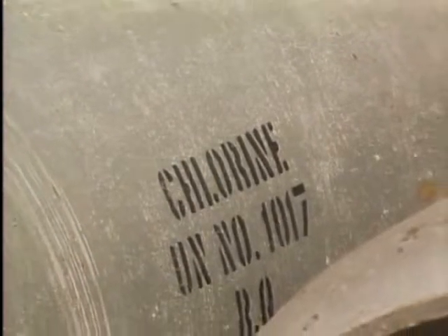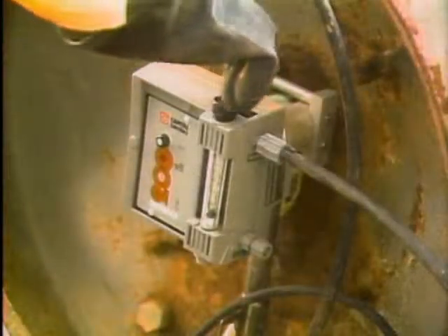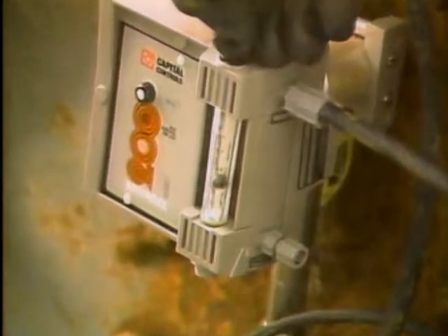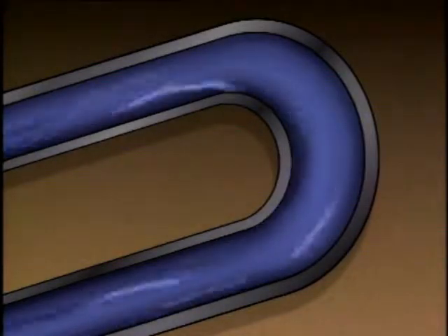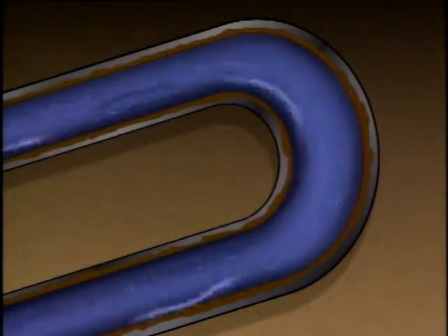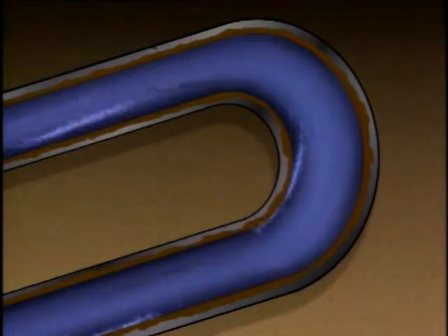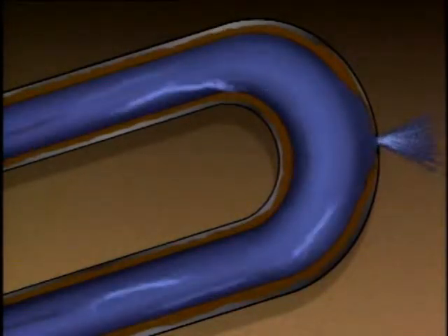Fouling can sometimes be minimized by adding chemicals to the fluids passing through a heat exchanger. For example, chemicals such as chlorine are often added to cooling water to reduce the amount of algae or other organisms inside a unit. Corrosion chemically deteriorates tube metal to create a leak. Corrosion is caused by a chemical reaction between the metal in the heat exchanger and either the fluid passing through the unit or impurities in the fluid. The corrosion weakens the metal until a leak forms.